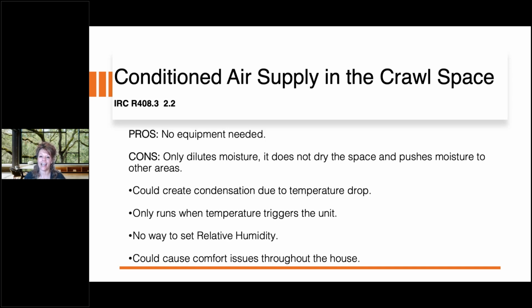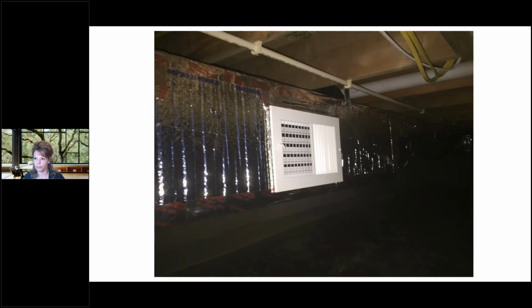So there is a huge benefit to educating HVAC contractors and our builders that as we start encapsulating these crawl spaces, really the only thing we need is a dedicated dehumidification strategy. We just need to dehumidify it. If we've air sealed it and insulated it correctly, there should not be that big of a difference in temperature. We're really just concerned about that moisture. So this is what that would typically look like. They're just popping in that supply register into the crawl space.